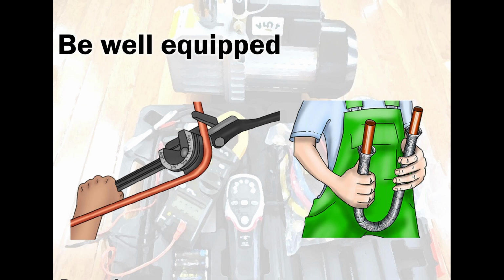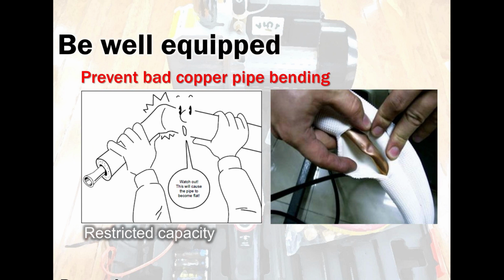Use your benders. Use your tools. Get a good clean bend. This guy was 40 years into the trade. And see what happened. He thought he got away with it because it was insulated. He thought he got away. But then when the compressor started running and shutting down on high pressure, that's where the problem came up. He cut open the corner, he cut open the bend, and this is what he saw.